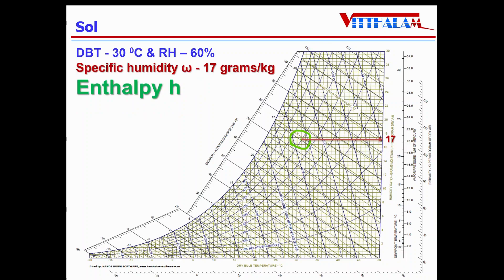Second property is the enthalpy. As we know, enthalpy is an inclined line. So from this point, if I draw an inclined line when it intersects the enthalpy line, the value of that, that is 75, is the enthalpy of the given air, that is 75 kilojoule per kg of dry air.